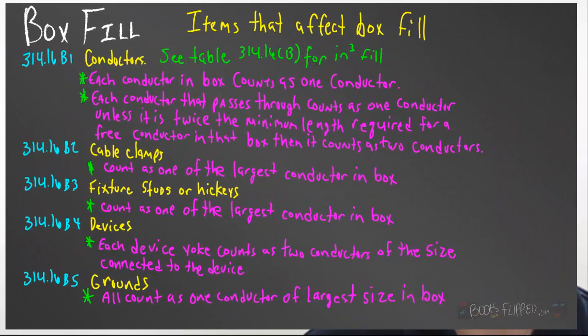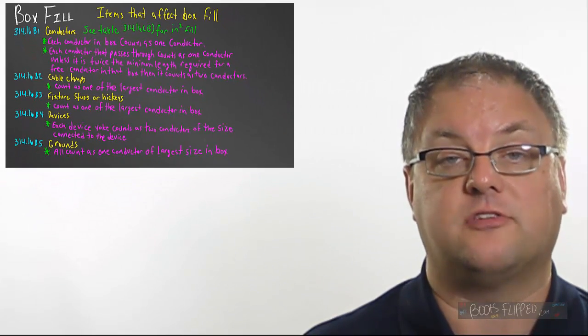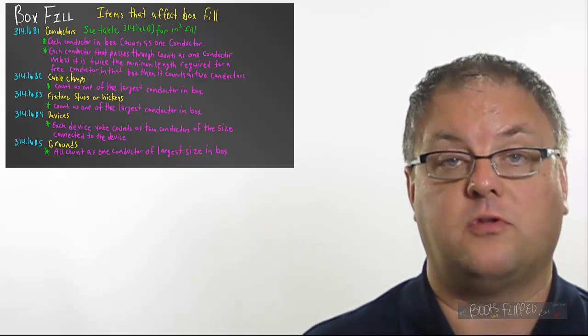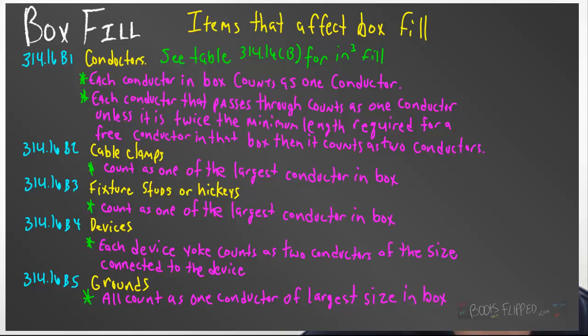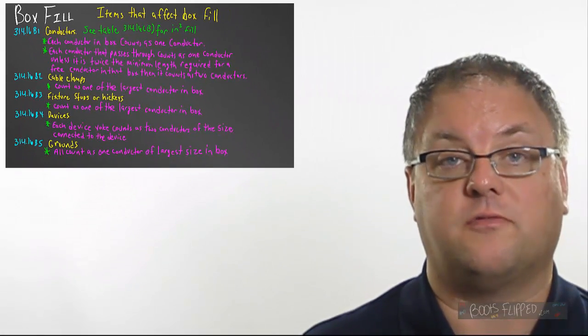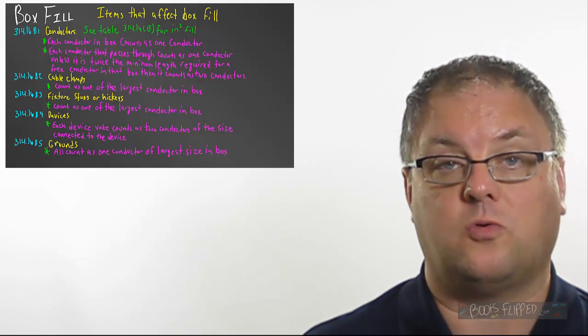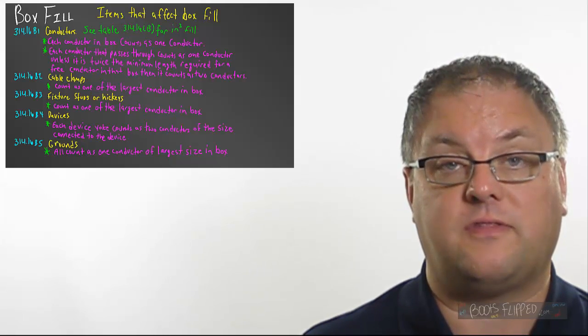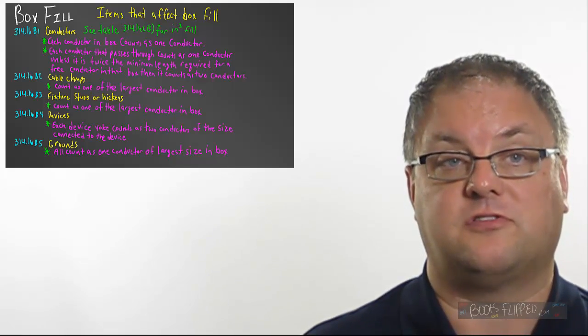In Article B2 of 314.16, it tells us that cable clamps inside of a box, they count as one of the largest conductor. So, all of the cable clamps together only count as one conductor. Remember that when you're doing your box fill calculations. In 314.16B3, we see that fixture studs and hickeys, not the kind on your neck, but those are fixture supports that go inside of a box, those also count as only one conductor. So, don't forget that when you're doing a calculation that you have a support for a box that has a light fixture in it.